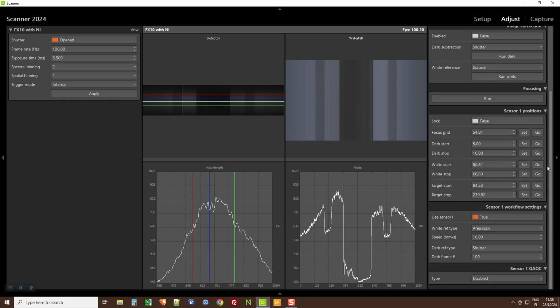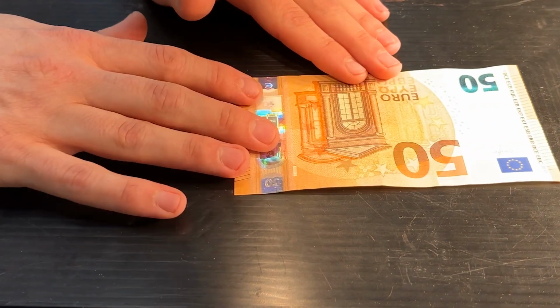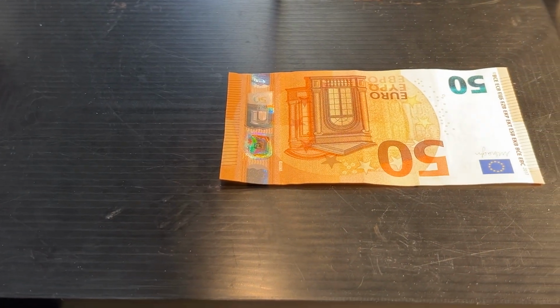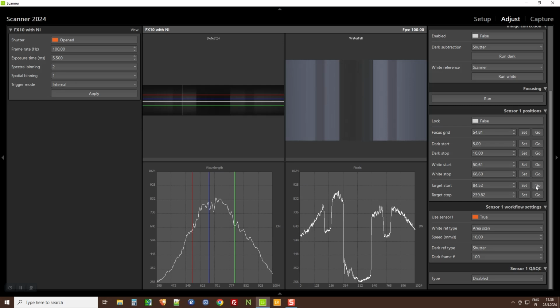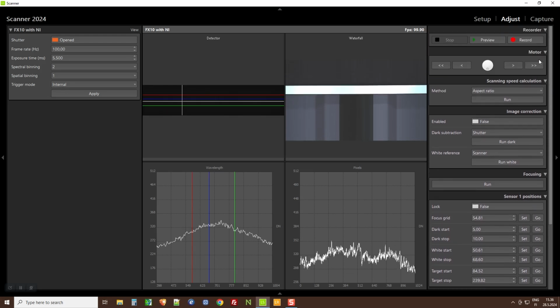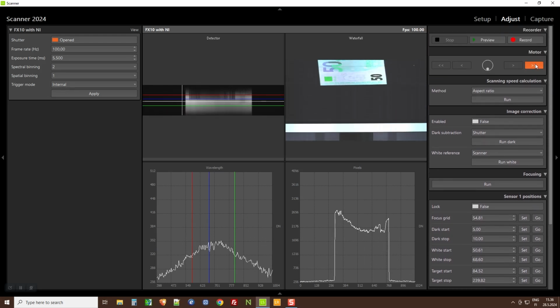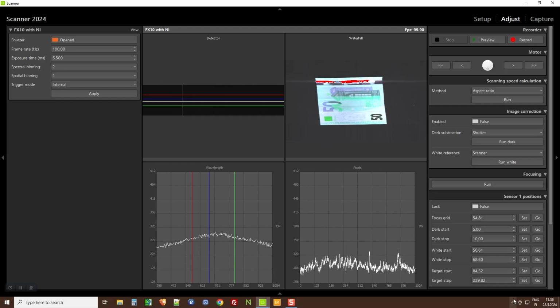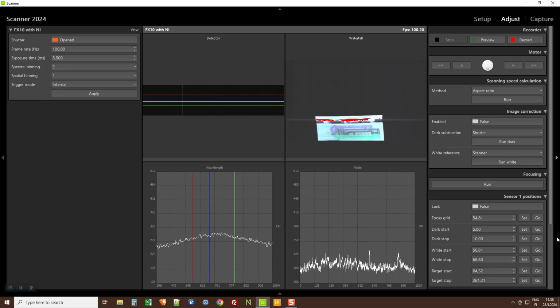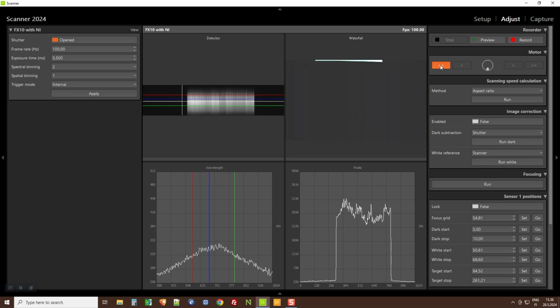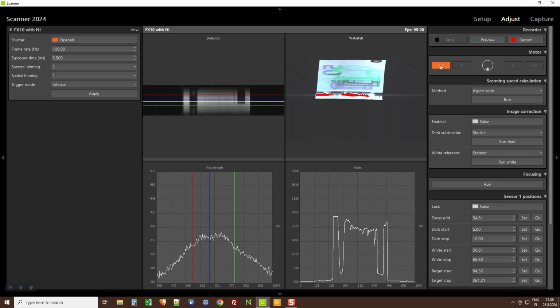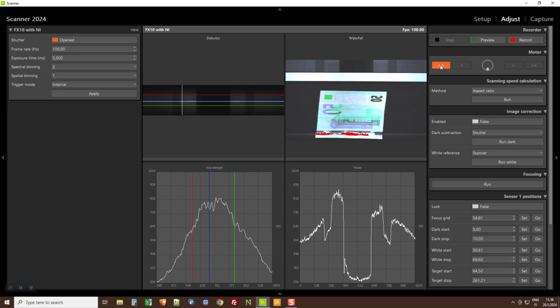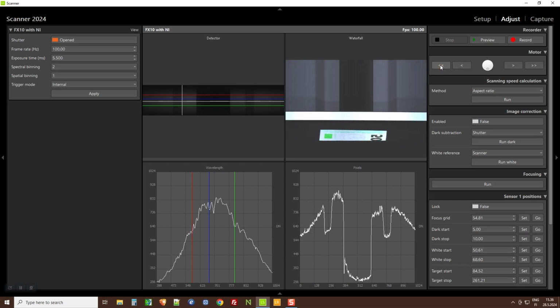So I can put the sample now on the tray. I will define again where is the target start and the target stop. So I will start with the target start to check if we're at the right place. Then I will move to the stop, somewhere here, set. Notice that part of the sample here was saturated. So I can decrease the integration time, or I can consider that it's not so dramatic because I'm not interested in those areas specifically. So I will do that.